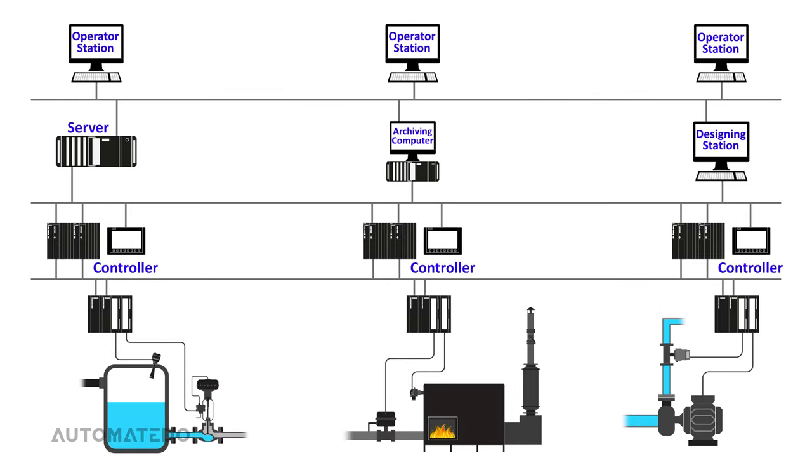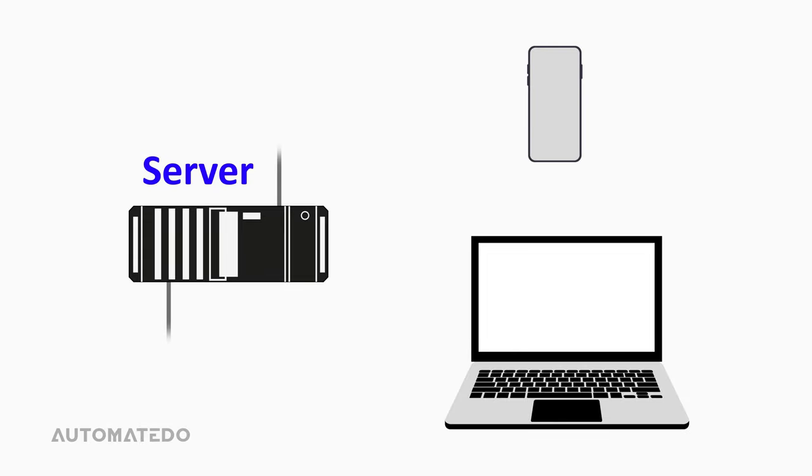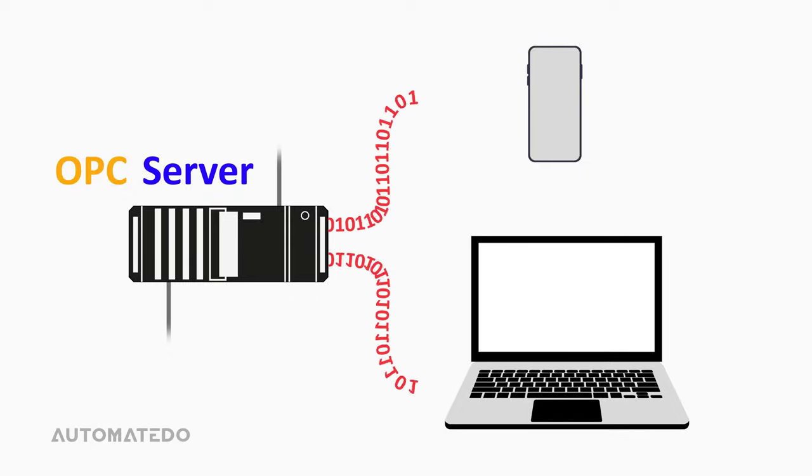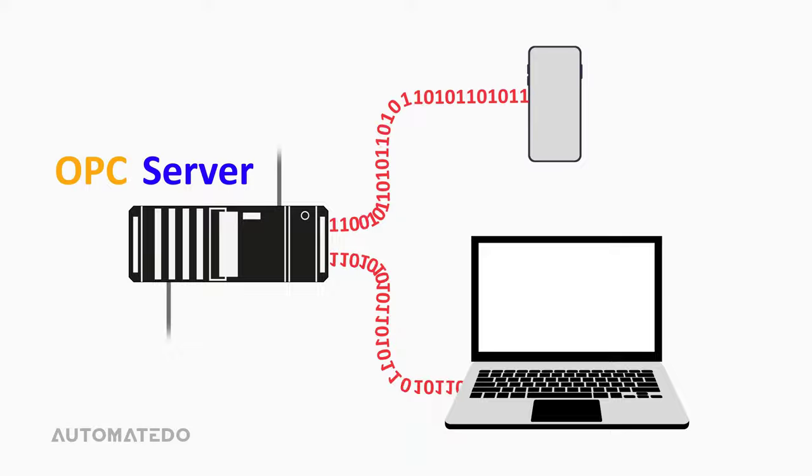Let's find out the purpose of using the server. The server is responsible for collecting data at the controller level. Its main task is to transfer data between the controllers and the operator stations. It's interesting to note that if the OPC server is used in our system, we can exchange the DCS data with any third-party devices that need the process control information.